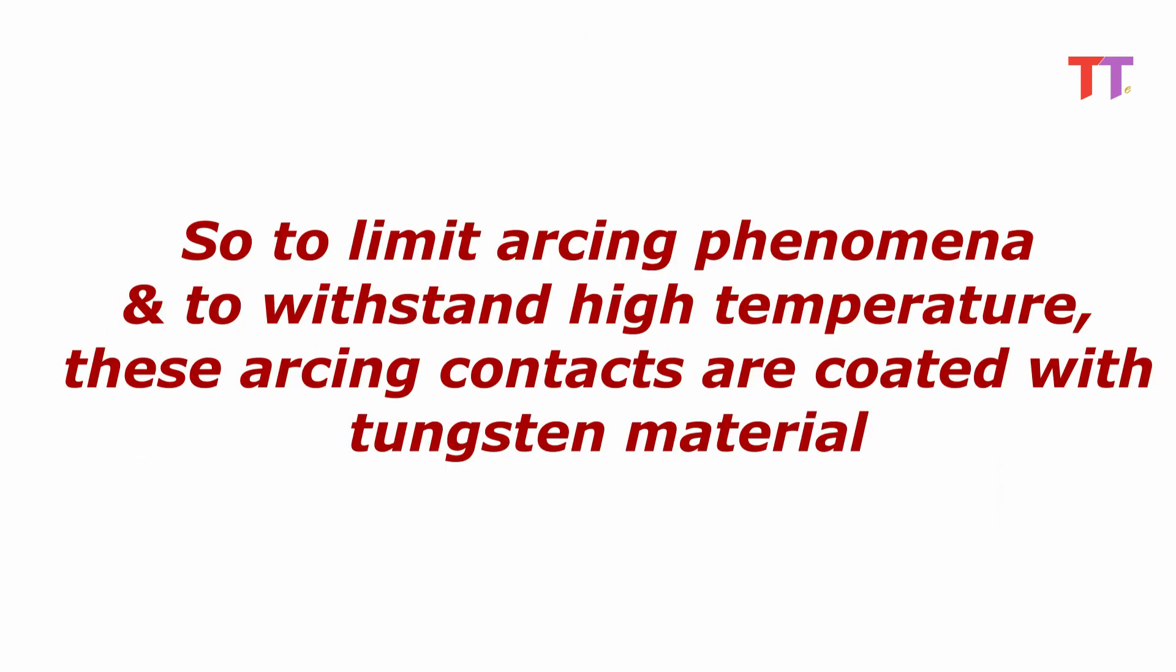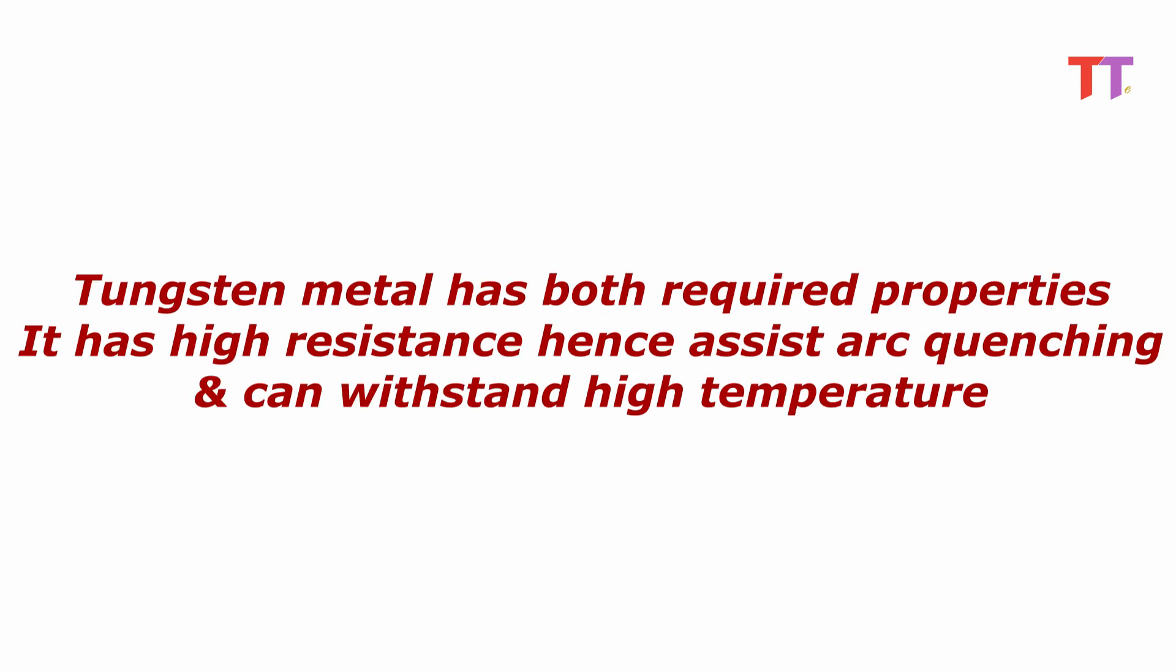So to limit arcing phenomenon to withstand high temperatures, these arcing contacts are coated with tungsten material. Tungsten metal has both required properties. It has high resistance hence assist arc quenching, and can withstand high temperature.